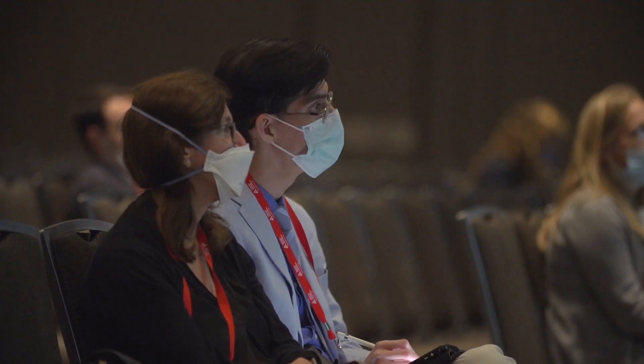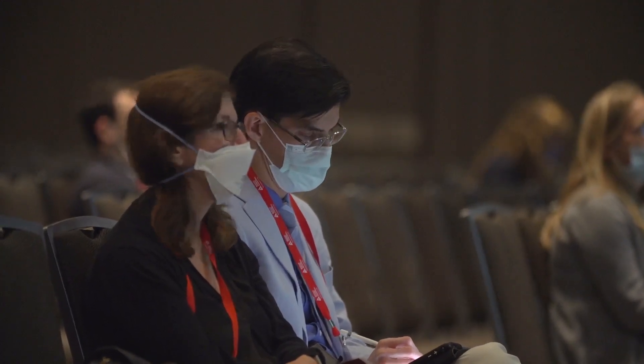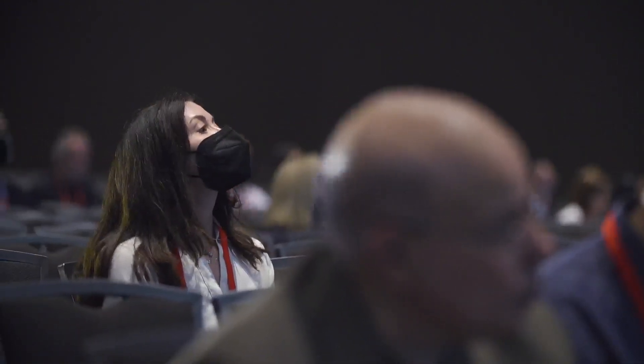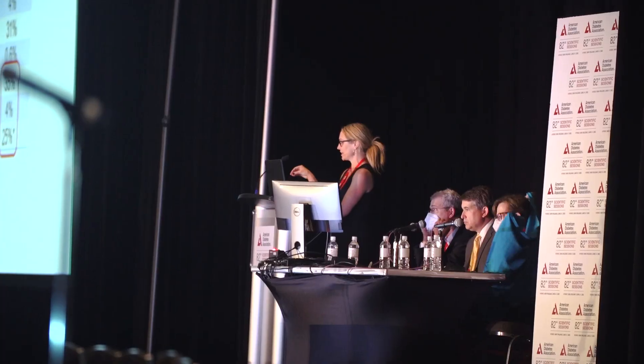It tries to give about 75% of the insulin needed for that meal. Another way it's different is that the device determines all of the insulin delivered autonomously — it's not possible for the person to determine the size of an insulin dose. They enter the meal size in a qualitative way, the device decides how much insulin to give, all correction insulin is given automatically, and all the basal is automatically regulated. Literally every single dose of insulin is entirely determined by the device.